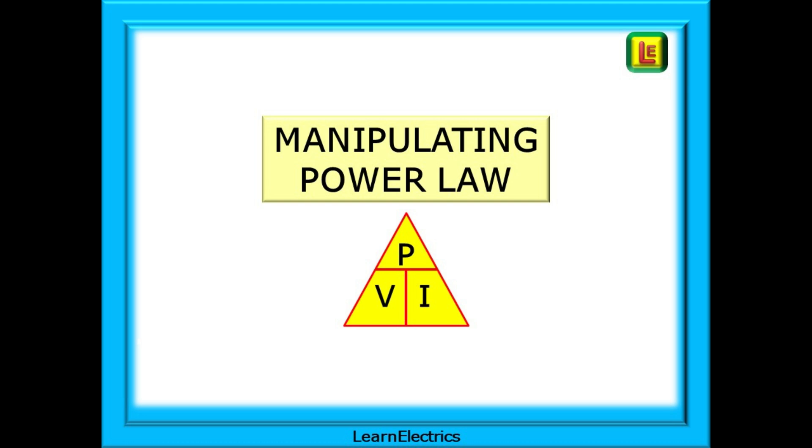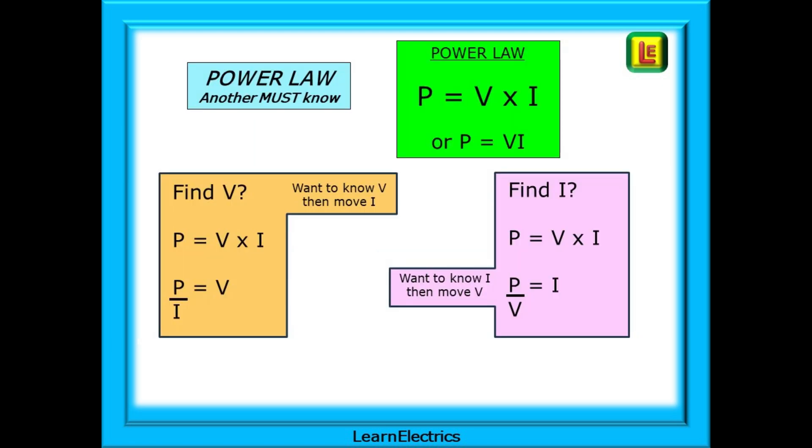Exactly the same method can be applied when manipulating power law. You will use this formula more times than you can count during your career as an electrician. When we install equipment, it usually comes with a rating plate marked in watts or kilowatts. But the rating plate doesn't tell us the size of fuse or breaker that we need. We need to use the power law formula to calculate the amps that the device will take. Power law is another must-know formula. P equals V times I. Power is equal to the voltage multiplied by the current.